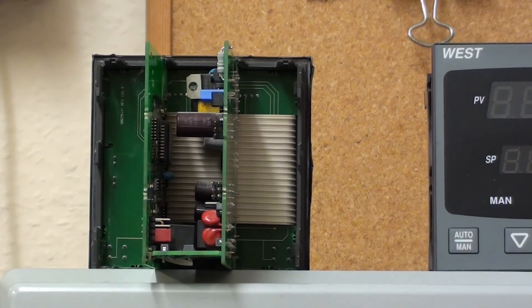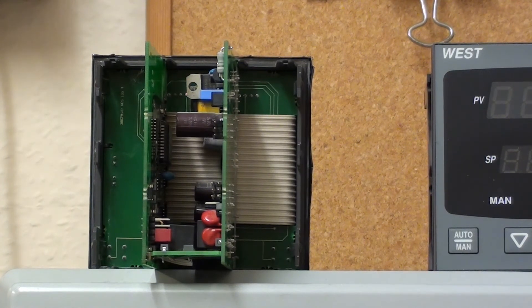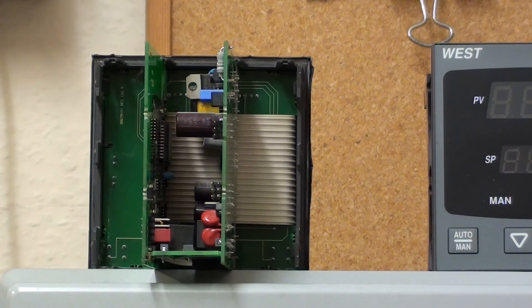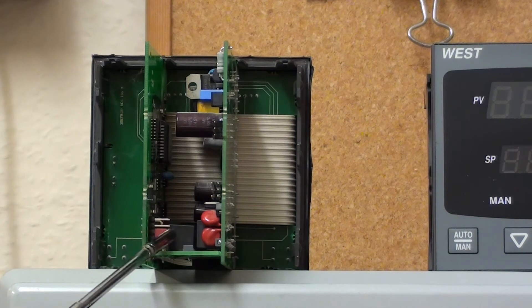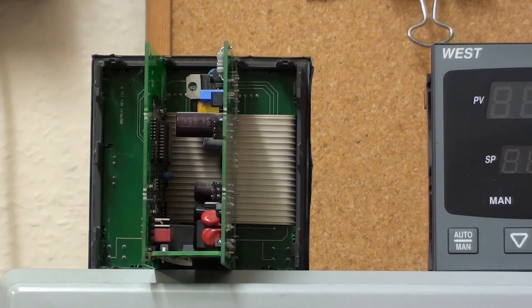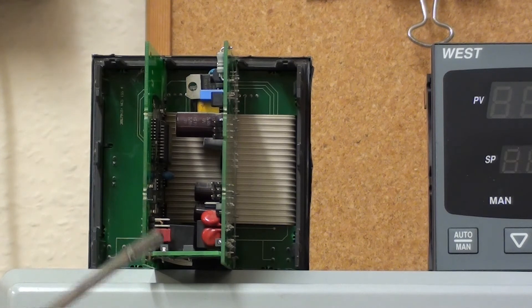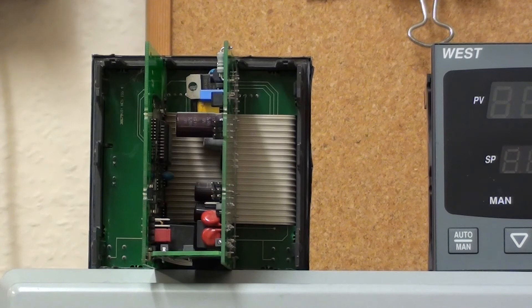I've taken the N4170 out of its housing and here we can see the internals of the controller. You'll notice on the N4170 there's a link jumper here. With the older controller it was necessary to position a link jumper for selection of the type of inputs that were required.